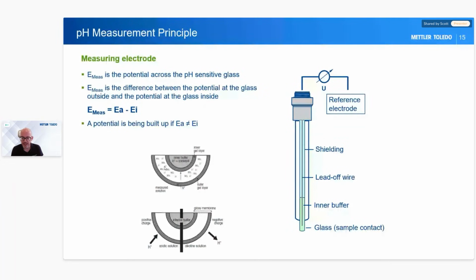One really good technique: if you go back to your labs today, as soon as we finish this webinar, you can take a look at your electrode, pick it up and look at the glass bulb end. What you'll find is the glass bulb end is normally a different color. It's really hard to show on the webinar, but if you take a look, it's normally tinted green or yellow, or maybe a little blue sometimes. That is the actual gel layer, and that's why the glass looks a slightly different tint to the rest of the glass electrode. That's because you've got this lovely gel layer on it.